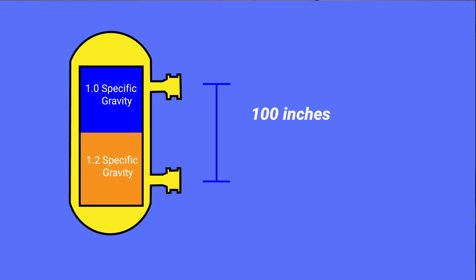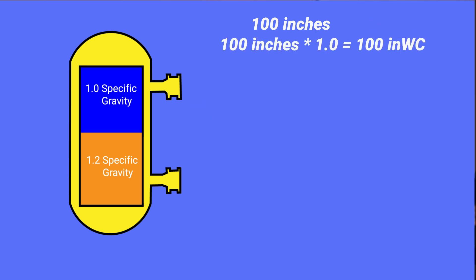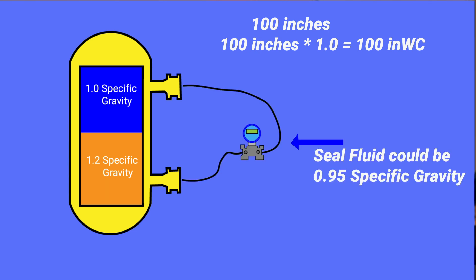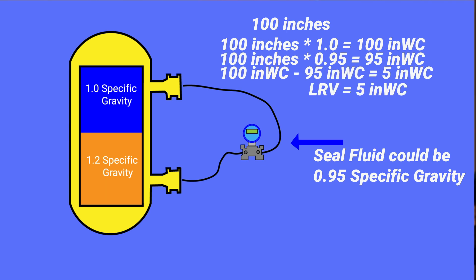Let's first look for the LRV. That will give us a 4 milliamp output from the transmitter. The formula is taking 100 inches multiplied by the lower specific gravity of 1.0, which is 100. Now let's subtract that number of 100 from the value of 100 inches multiplied by the specific gravity of the seal fluid inside the capillary, which could be 0.95. That would be 95 inches. So 100 minus 95 is 5, so the LRV or the lower range value will be 5 inches of water.